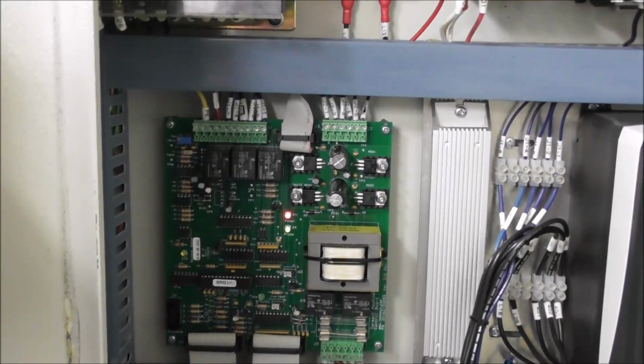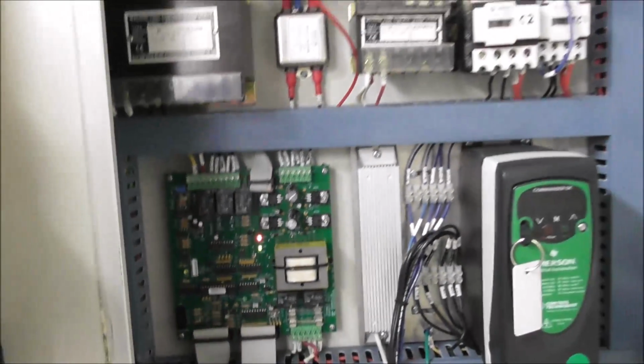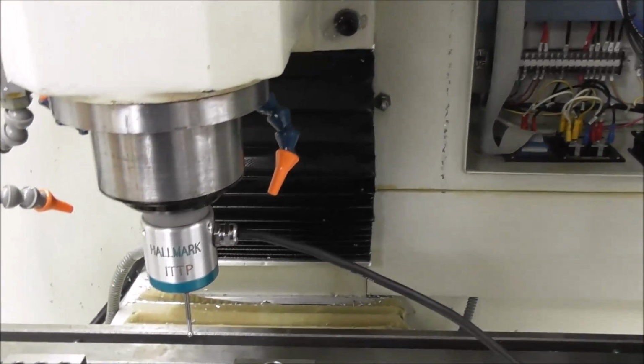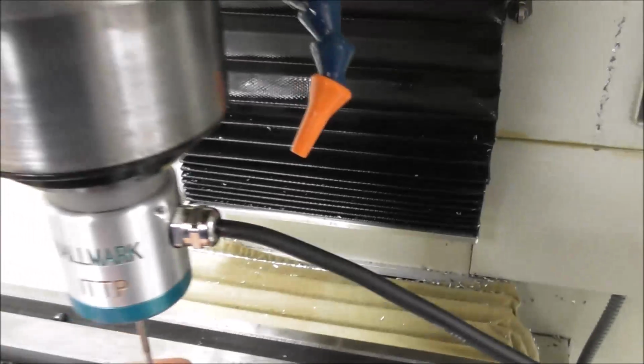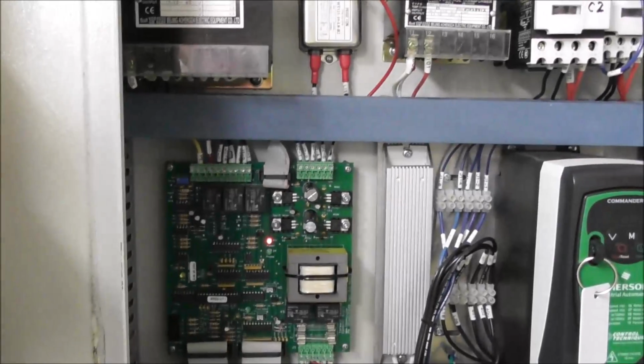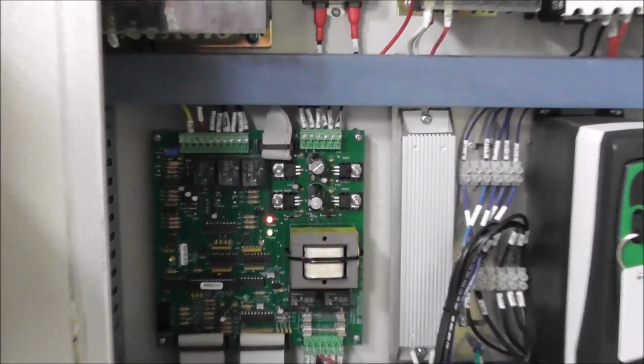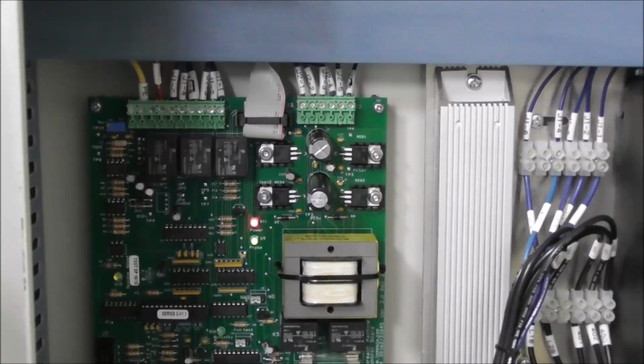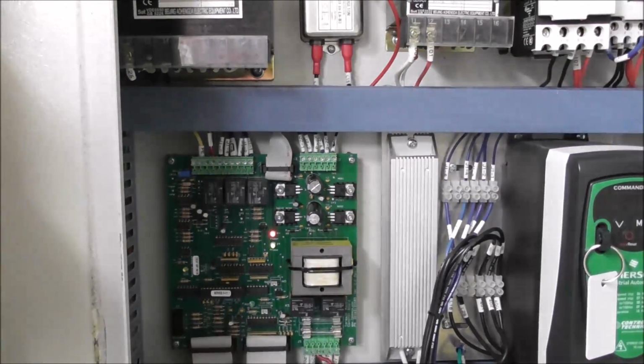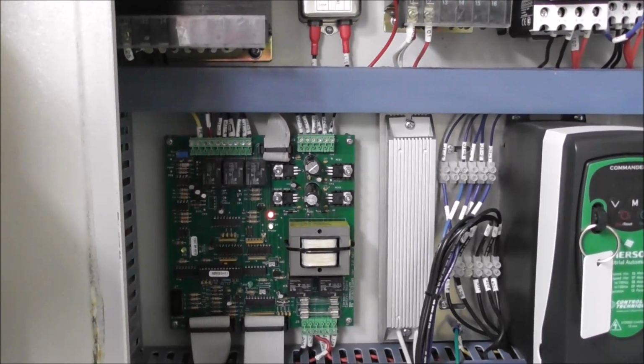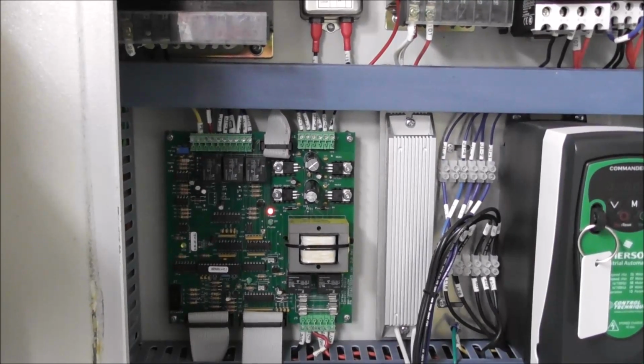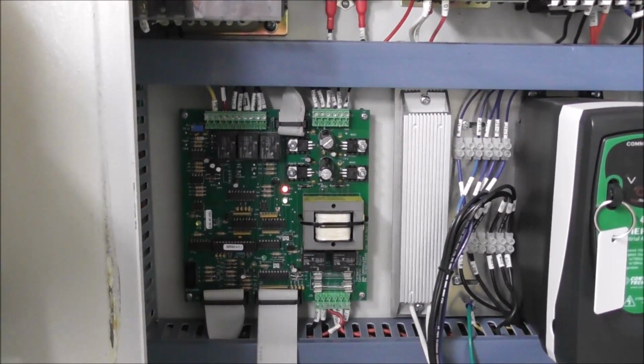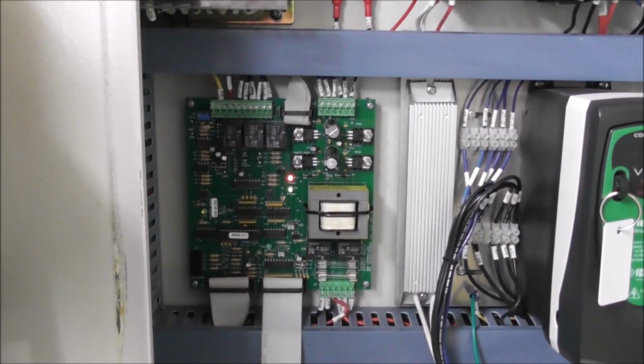Now what happens is, when the probe's plugged in, the circuit is live. There is electricity flowing through the probe, and if I trip the probe, here I'm just moving the probe mechanically, you can see the little LED going on and off. So when the probe is plugged in, that circuit is live. When the probe is tripped, it sends a signal through to the opto-isolator, and that trips the software.